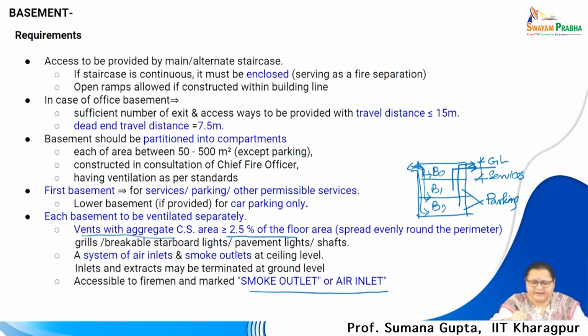Now, these points are narrated here. You see, the first basement is for services, parking and other permissible services; lower basements are only for parking cars. Also remember, the dead end travel distance is 7.5 meters to any access in case of a basement. Sufficient number of exits and access ways are to be provided within the travel distance of 15 meters, and from the dead end it should be 7.5 meters. So, from the basement the escape should be very quick.